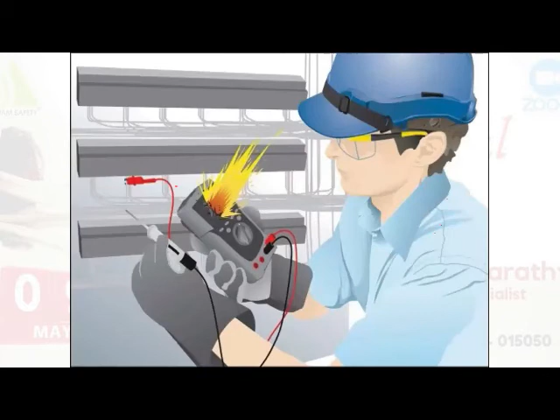Even a measuring instrument itself can create an arc flash. If a person holds a measuring instrument and views the reading very close to his face, in case of wrong equipment it may blast. So while measuring, the person should have proper face protection—a helmet alone is not enough, eyewear goggles alone are not enough, it's always better to provide a proper face shield.